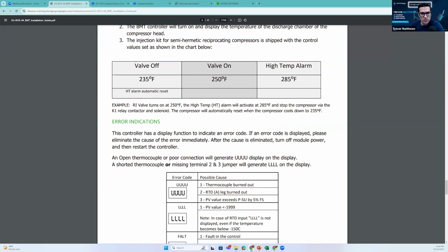Got a question here. Why would you want to do liquid injection versus a two-stage compressor or a higher differential compressor that can handle it without injecting? There are different reasons for that. You can't always get a two-stage compressor for certain refrigerants. Not all manufacturers have two-stage compressors. Bitzer has a two-stage compressor, but it's not for all applications. And that's a great question. I don't have an answer for you.